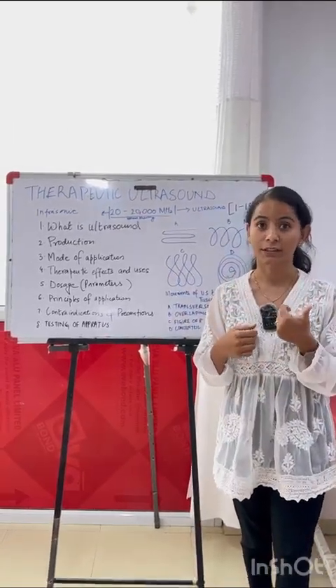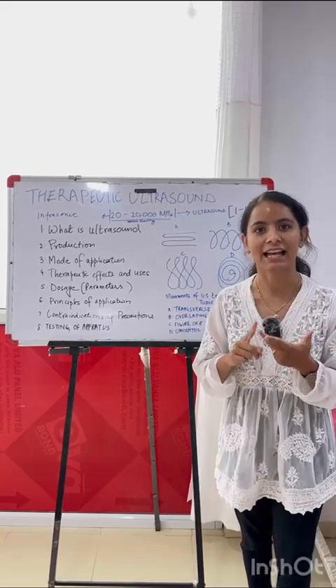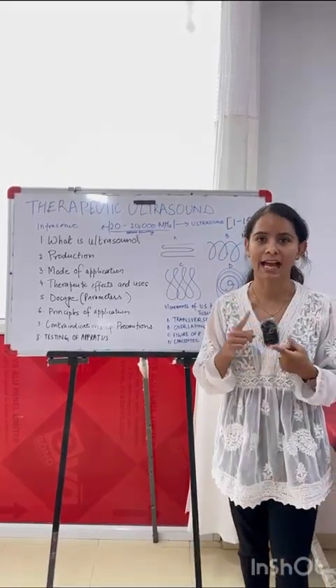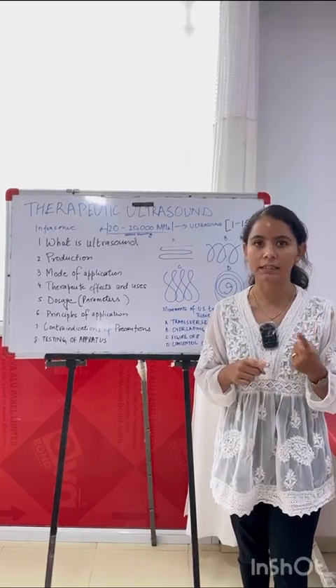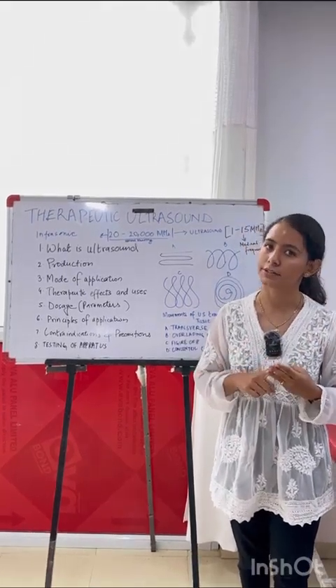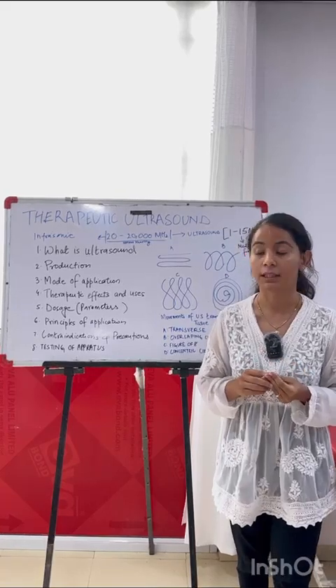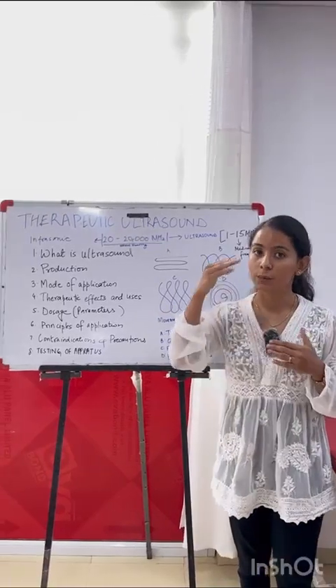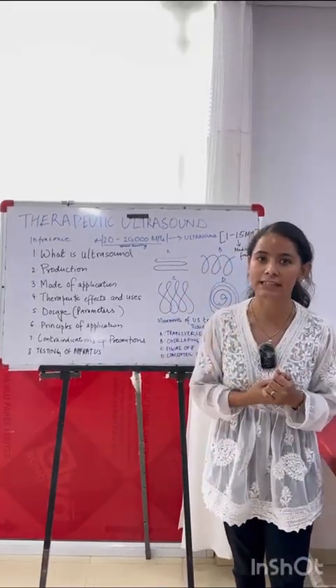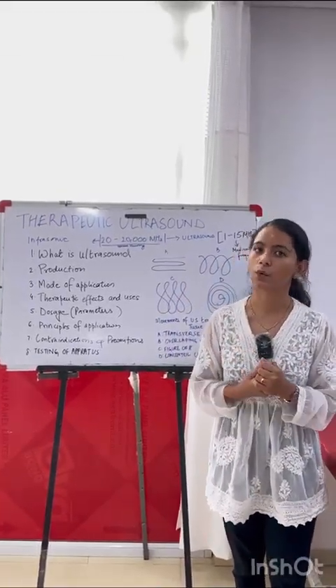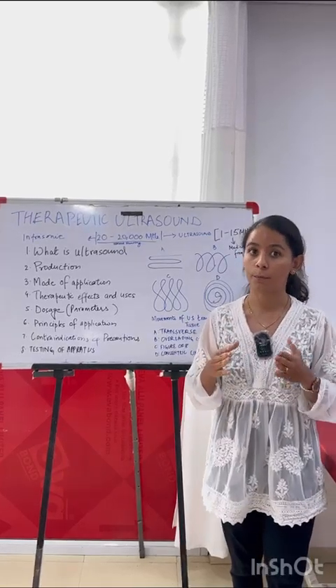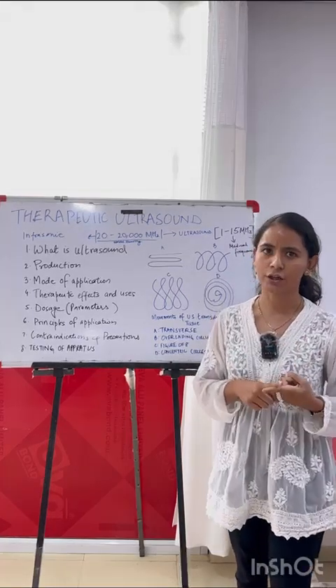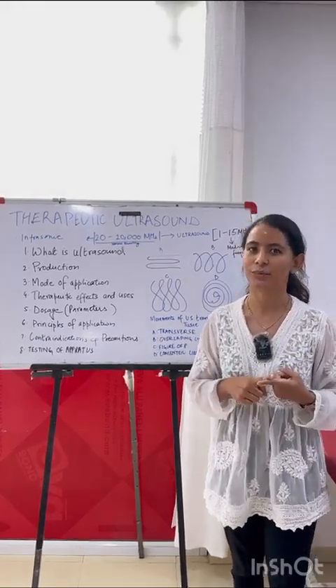For the parameters for dosage, there are four parameters: mode, frequency, intensity, and duration. Mode, as we discussed, has two options — continuous and pulsed. For frequency, we use 1 MHz and 3 MHz for ultrasound application in physiotherapy; the medical frequency ranges from 1 to 15 MHz. As the frequency increases, the depth of penetration decreases. The unit for intensity is Watt per centimetre square, and the intensity ranges from 0.1 to 1 Watt per centimetre square. For duration, we need to check the condition and decide accordingly.